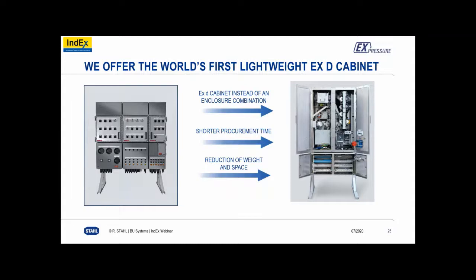Then when we look at installation, the installation of this cabinet on the right would be much quicker. So in countries such as Australia, UK, Canada, America, even other EU countries, the installation time is much less, with less chance of mistakes. If we're talking about offshore, well, reduced weight is reduced costs. Reduced parts and components is reduced costs. They don't need to be flown or shipped offshore to a vessel. And then installation time, maintenance time and operational checks.